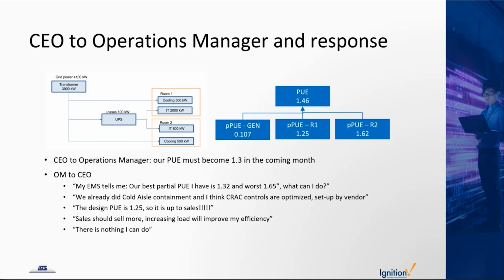And to be honest, if you look at the design PUE of our data center, it's 1.25. But the reason that it's so high is not because of me, because I did everything I could, it's because of sales. I see that room 2 is hardly filled and sales should sell more. And if room 2 is also filled, then we are within the range. So go to sales, there's nothing I can do. And actually this is quite a normal situation because in general, an operation manager has mainly his PUE to manage and control and optimize his data center. So he has no more ideas how to improve anymore.